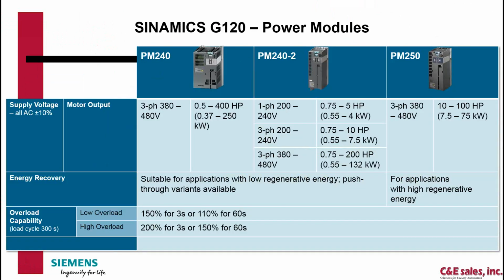Here's some of the power modules. This slide shows PM240. This slide's a bit dated, so actually most of the 240s have been replaced by the 240-2, just a newer generation of the drive. Here it's in single phase, 200 to 240 volt, 3/4 to 5 horsepower range, 3-phase in the 200 to 240 volt, 3/4 to 10 horse, and then at the 380 to 480 volt range, 3/4 up to 200 horsepower in the PM240-2. Above the 200 horsepower range, we revert back to the PM240 for now.